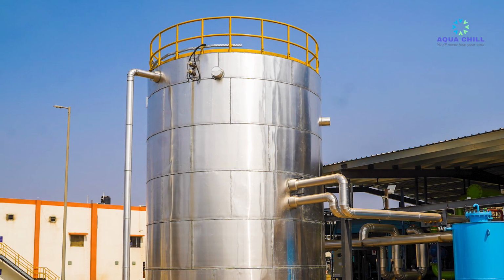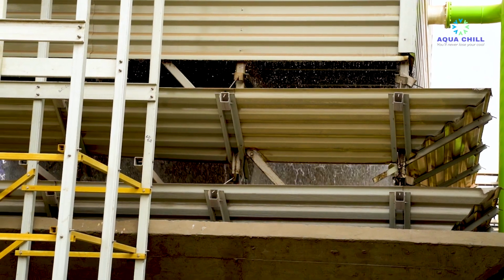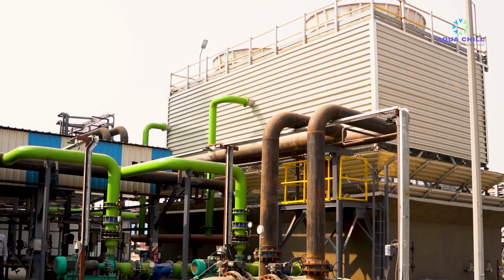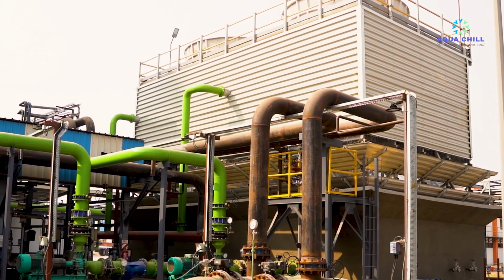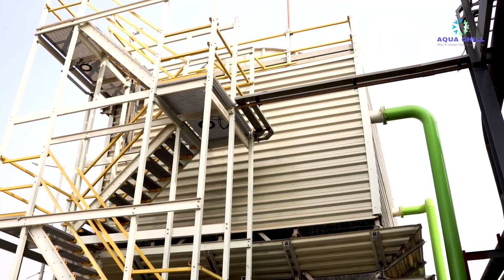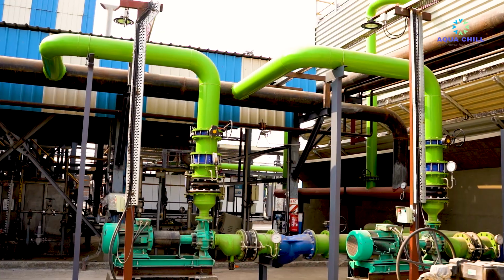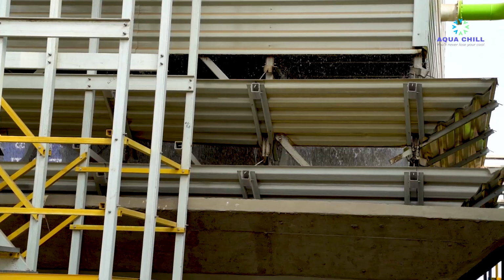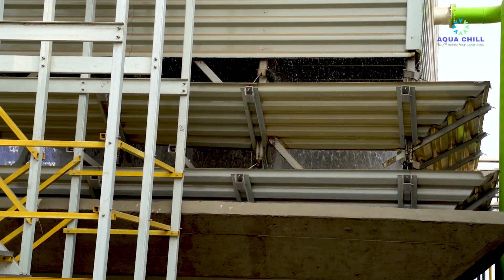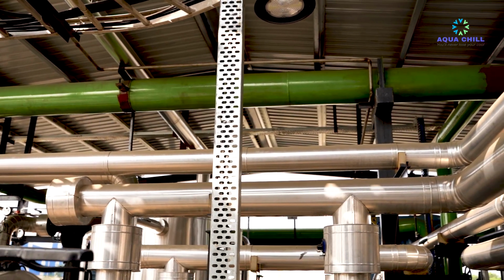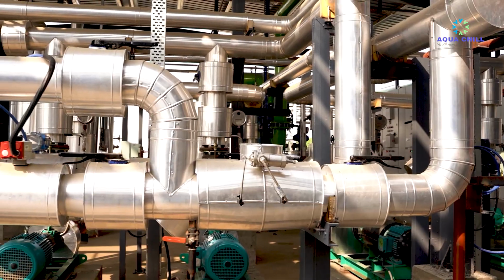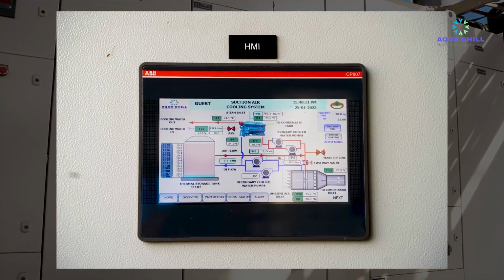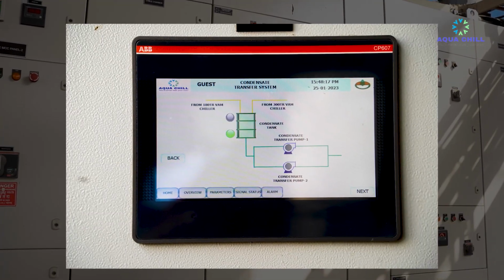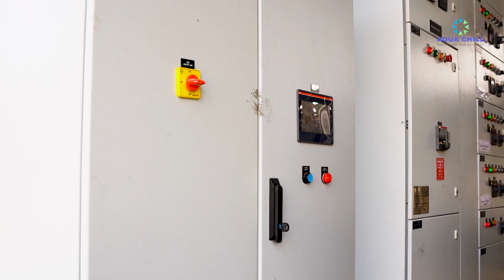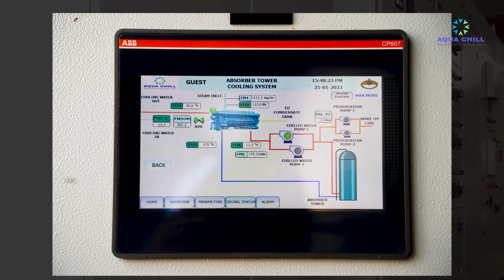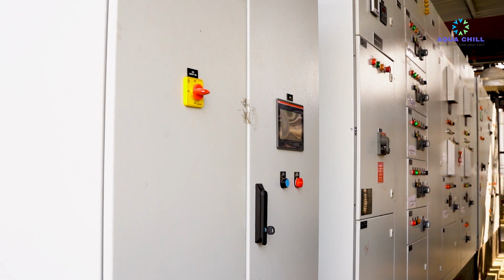This system has further helped in reducing the energy consumption of cooling water pumps and cooling tower fans, which are of fixed consumption irrespective of the cooling demand. It has also improved the COP of the chiller, as a substantial amount of chilling is generated during night time when the condenser heat is dissipated at a much lower temperature. All these parameters are monitored, recorded by a full-fledged instrumentation and PLC system. This innovation is first of its kind in India as far as our sphere of knowledge goes.